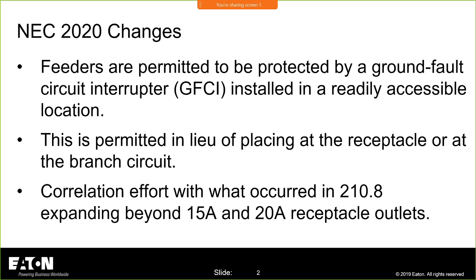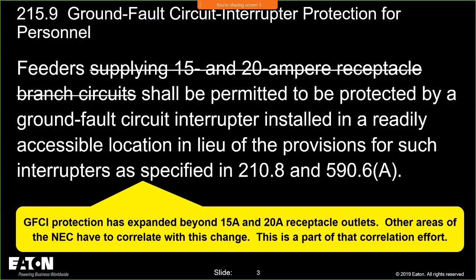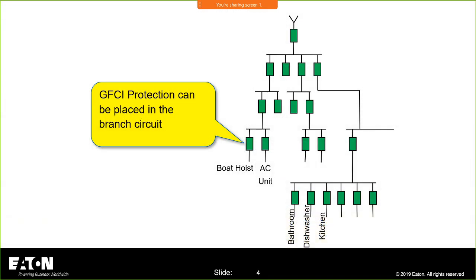And again, it correlates with what occurred for the 15 amp and 20 amp receptacle outlets. Basically, if I place the GFCI in that branch circuit for that boat hoist, or I could put that GFCI protection up there in the feeder instead. And the only thing you have to think about is the further up in this system...